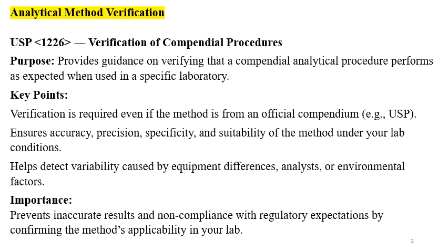Key points are verification is required even if the method is from an official compendium like USP. It ensures accuracy, precision, specificity, and suitability of the method under your lab conditions. We need to check and verify the reliability and workability, you can say, for the compendial method. This analytical method verification helps to detect variability caused by equipment differences, analysts, or environmental factors.